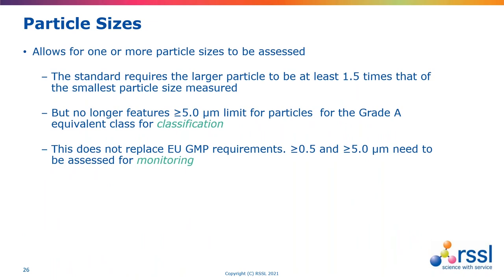Because these standards are not directly GMP, there are variances in particle sizes and cutoffs. Under FDA, the concern is with particles equal to or greater than 0.5 microns. Under EU GMP and Annex 1, the emphasis for operations is on particles of 0.5 microns and greater, and five microns and greater. The revision to Annex 1, as it currently stands, will state that for classification of grade A only 0.5 microns needs to be assessed, with the option to use large particles. For routine operations, both particle count sizes need to be continuously assessed.